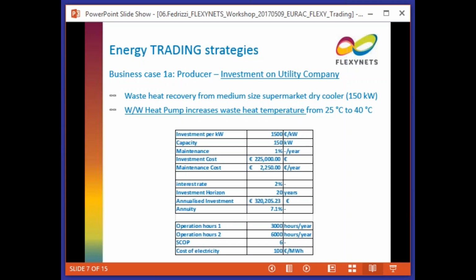From the financial point of view, the investment is borne by the utility company, so there's no economic burden on the supermarket. In this calculation, we consider something like 1,500 euros per kilowatt for the substation with a capacity of 150 kilowatts, as I said, which results in an investment cost of around 225,000 euros, and which corresponds over 20 years to an annualized investment of around 320,000 euros.